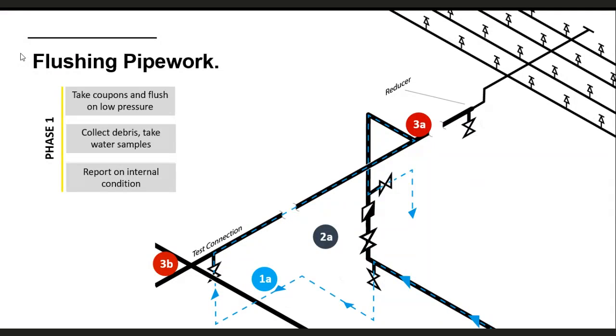So if you flush in that direction, you're going to push debris into where the pipe reduces in size. Whereas if you flush the other way, pushing from small bore into large bore, you're not going to have that effect, and you're going to flush the pipes more effectively. It doesn't actually tell you to do that in the standards, but that's a suggestion from me, and a suggestion from my former director, to do it in that direction.